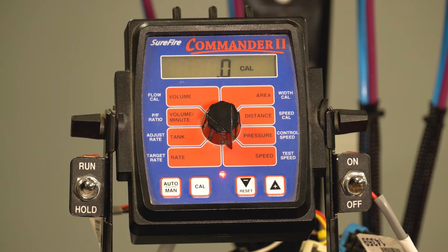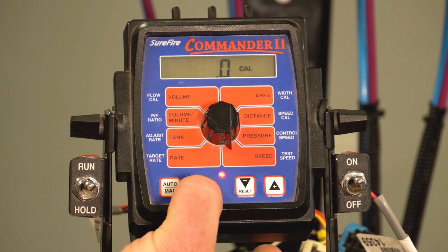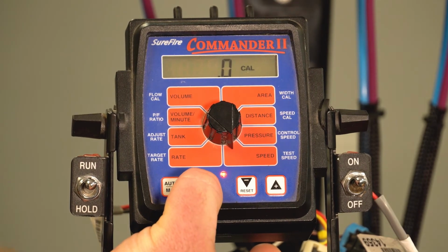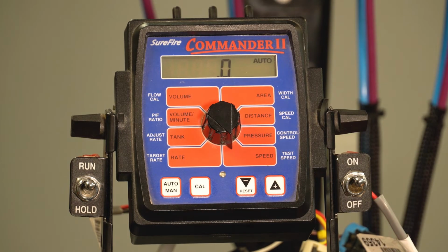So to finish with the calibration, we simply need to save those numbers. We would hold down the cal button just like we did to get into it. Hold it down, light goes away, and those cal values have now been saved in the system. And we are ready now to operate the system as we have calibrated it in standard calibration mode.